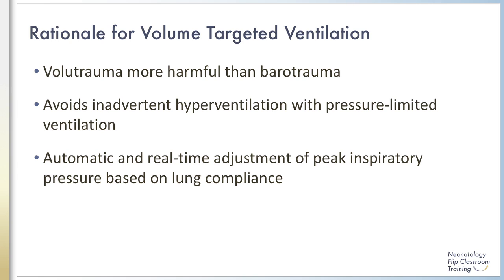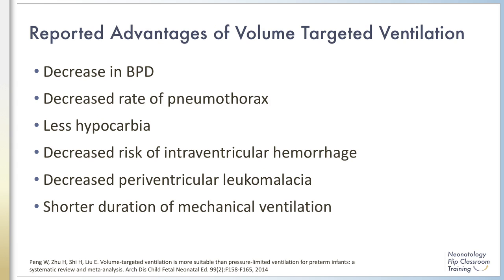With volume targeted ventilation, tidal volume is the controlled variable and the inflation pressure will vary with the lung's compliance. For safety, peak inspiratory pressures are limited. As lung compliance improves, volume targeted ventilation results in automatic and real-time weaning of the pressure, instead of manual decreases as would be needed in a pressure control ventilation modality. Conversely, a decrease in lung compliance will result in an increase in pressure needed to deliver the set tidal volume.